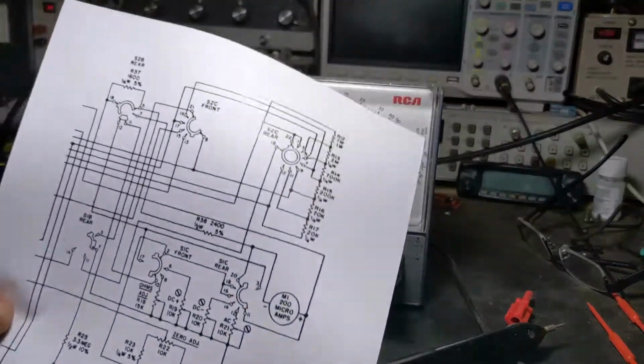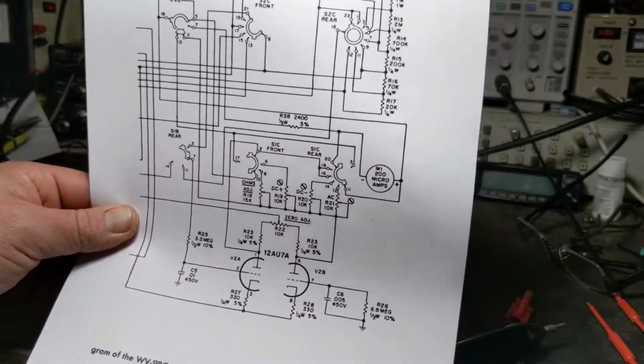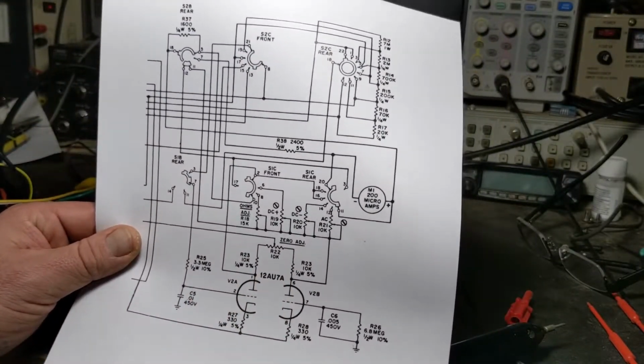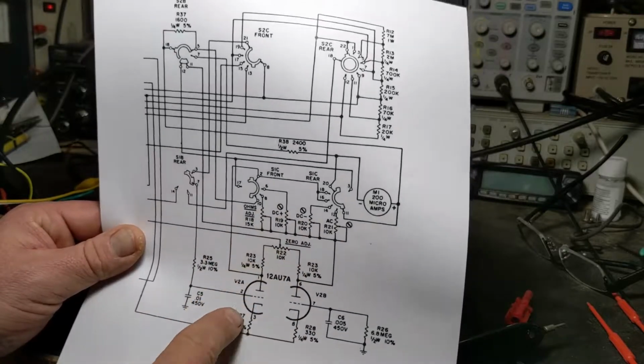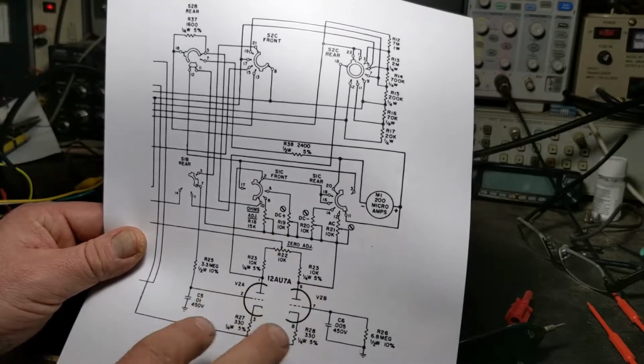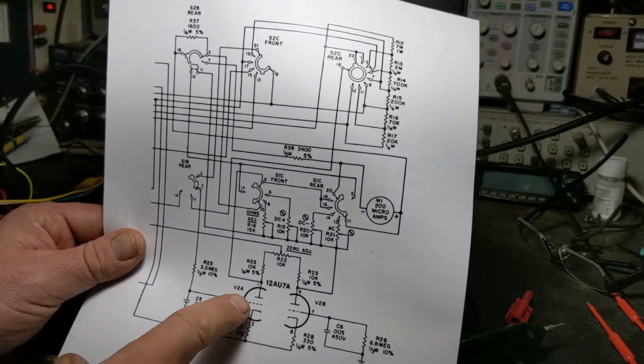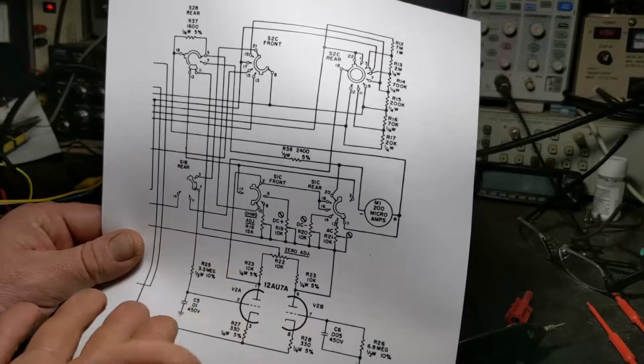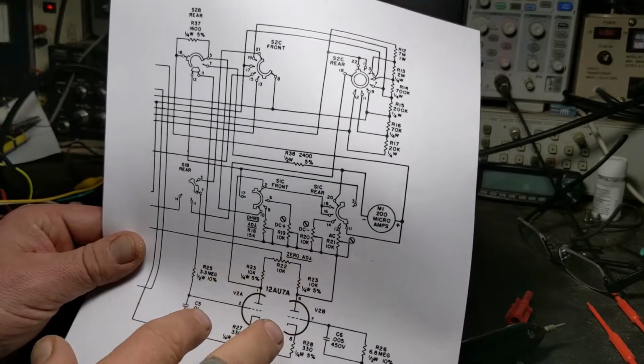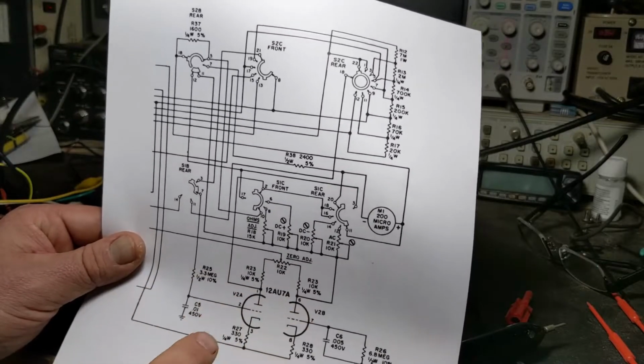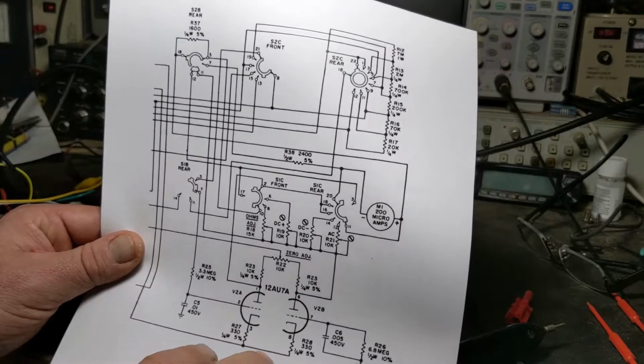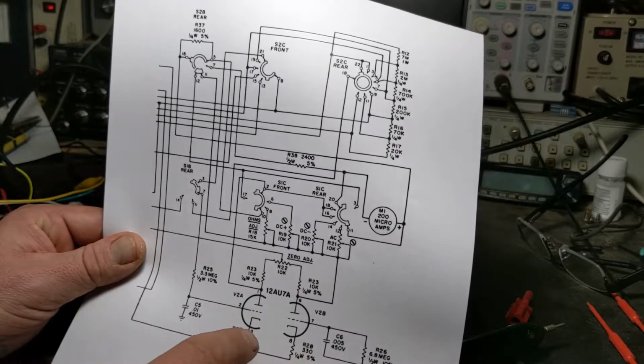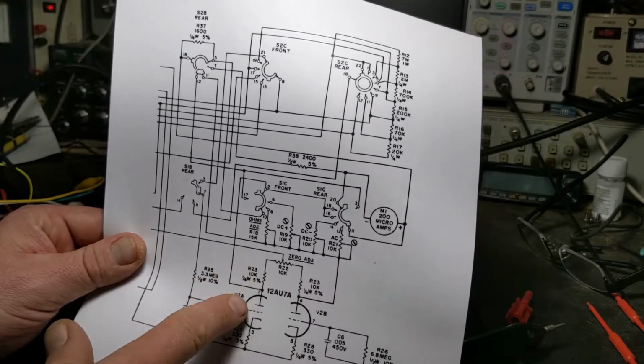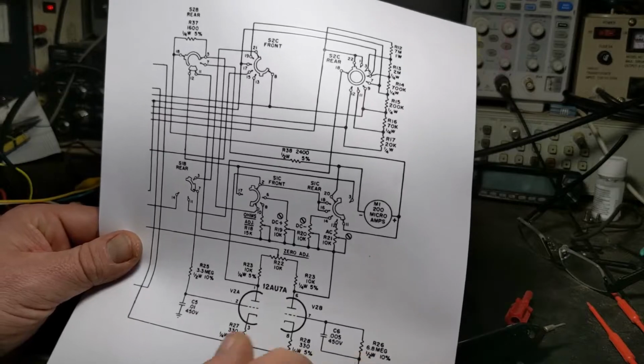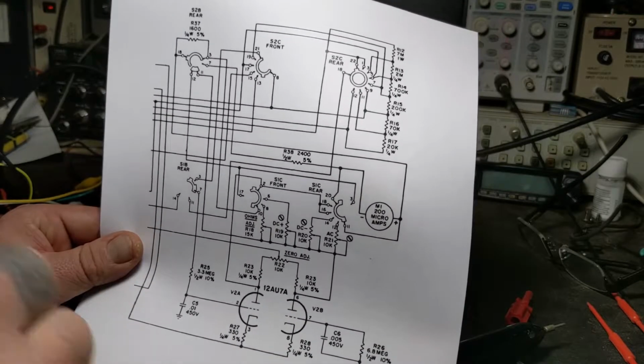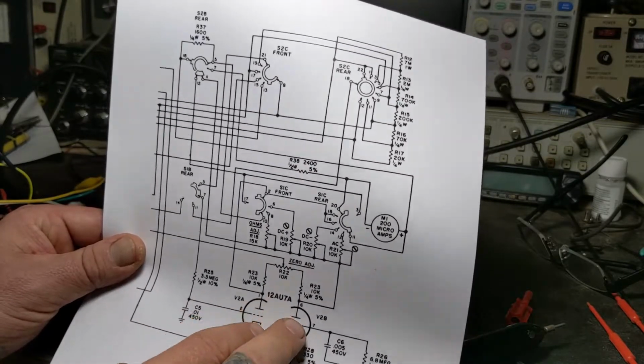It's on 2 pages here. Here's a schematic, this tube here. See how it's making a balance here? And if you can't get that, then this tube, one side's, that's what the 0 is for. If this tube could be in a perfect world where both sides match perfectly, you wouldn't need that 0 set. But it's not a perfect world, and one may be a little more tired than the other side or whatever, so that's what the 0 is for. If it gets to the point where you can't 0 it out, then you can probably replace that tube.